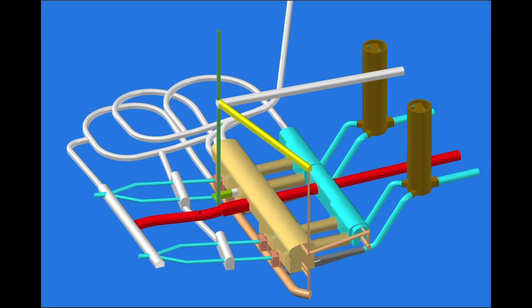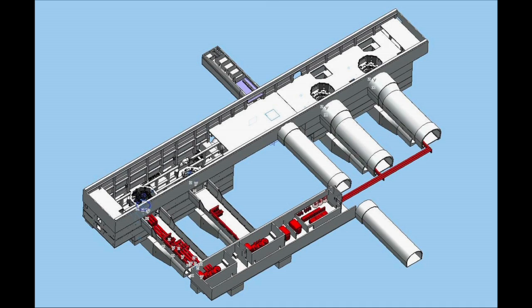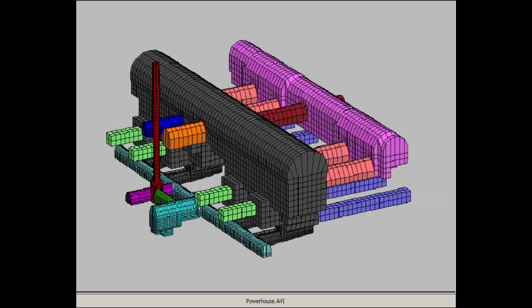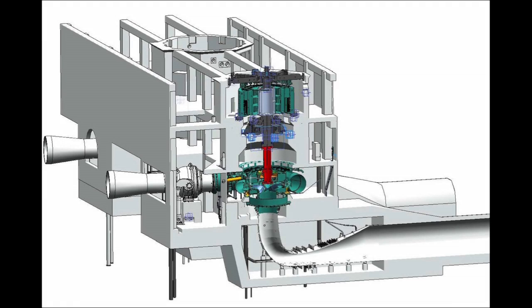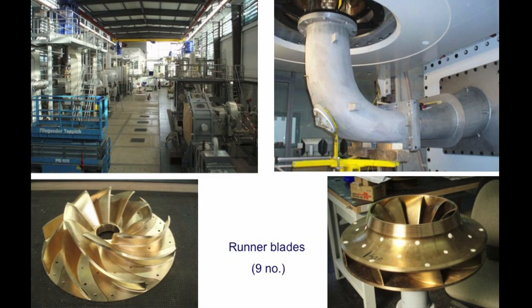The machine hall and transformer hall. Machine and transformer halls, linked by the bus bar tunnels. Various adits, waterways, outlet, ventilation. Typical section of the 2 caverns. You can see it's a vertical turbine, generator and runner with a ball valve, the main inlet valve, spherical valve. We modeled the underground by 3-dimensional FLAC analysis, just to get a feel for the stresses and to design the rock support system.